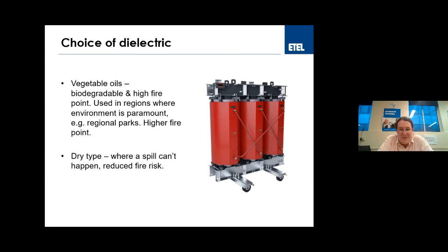The first one is vegetable oils. When I was working on a project about 15 years ago in Sydney, the utility in that area was looking at vegetable oils because they had a very high fire point, which was seen as preferable for use in some underground substations. Another utility was very interested in its biodegradability, since they had substations in national parks. You can't have spillages of mineral oil there, so this is where they were looking at vegetable oil - if a spillage does happen, it's easier to clean up.